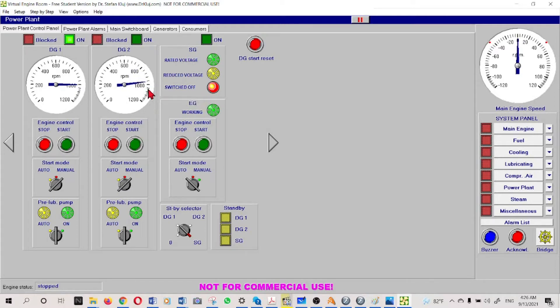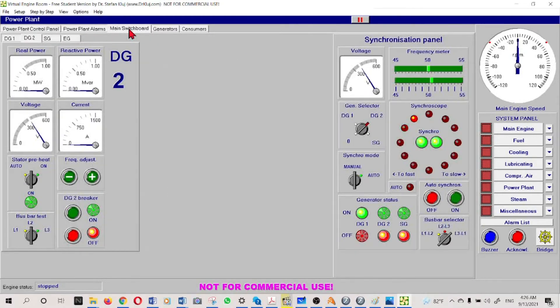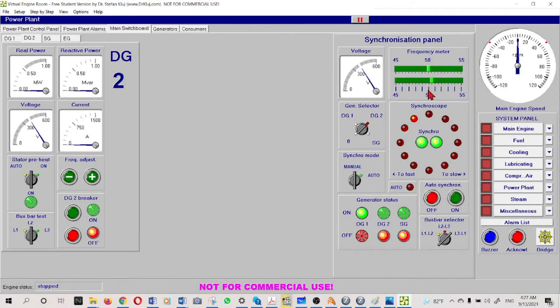Diesel engine number two - start switch - okay, we can hear the generator has been started and its RPM set value is 1000. Now it's running. We will move to the synchronization panel. Number two is still not connected to the bus bar. Now we can see the voltage is appearing - that means the EMF is being generated - and the frequency meter is now visible.